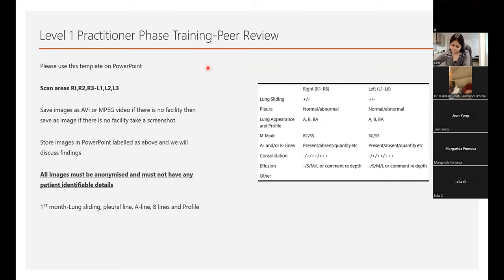The most important thing is you will need to increase your depth if it's vascular and MSK. MSK usually presets to a depth of about 2 centimeters—you really need to go up to 4 centimeters. Importantly, very small babies will need a higher frequency.